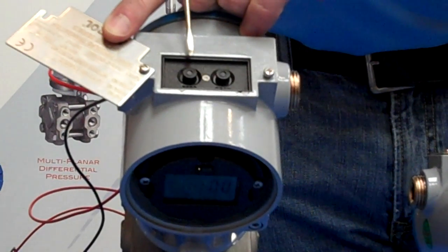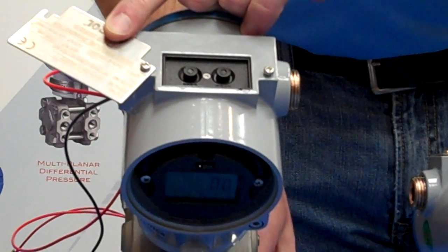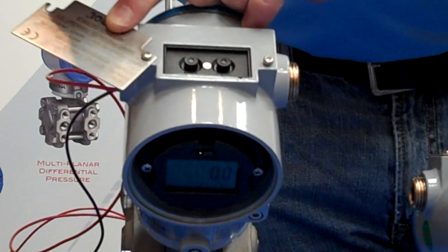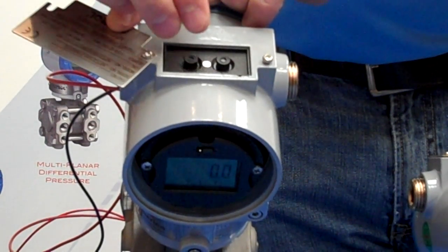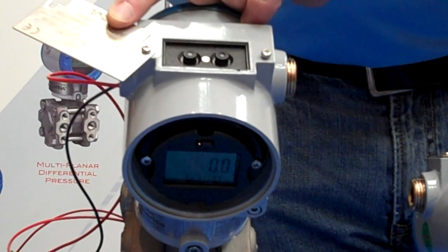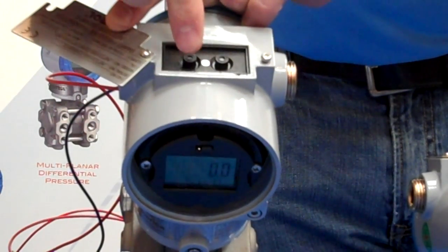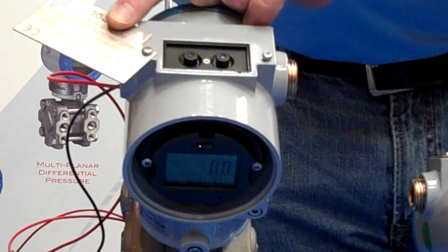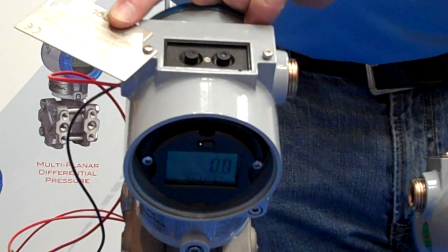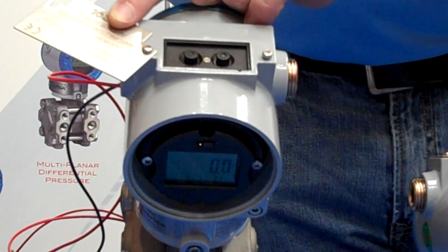We are going to use these two buttons to access the programming modes. One thing to note before we get started is that to actually enter configuration modes, we push them both together. If we push one or the other separately, that's going to be utilizing a different programming technique which will require a pressure source.